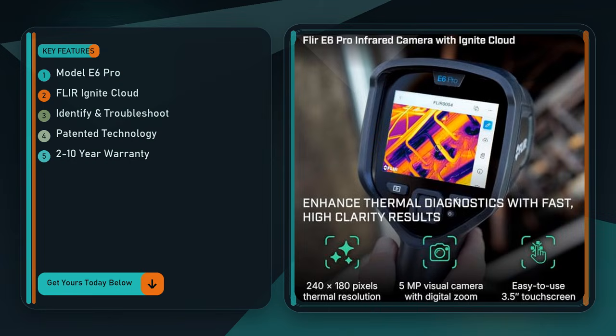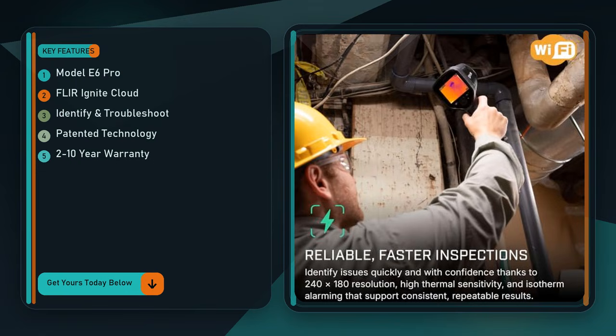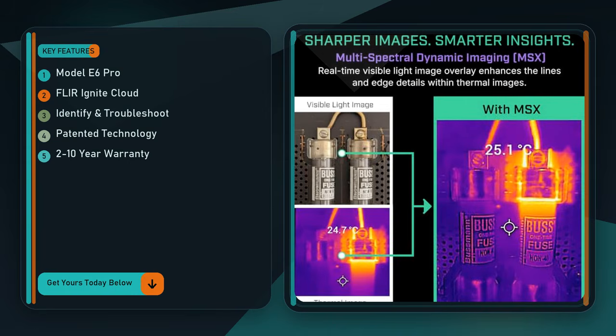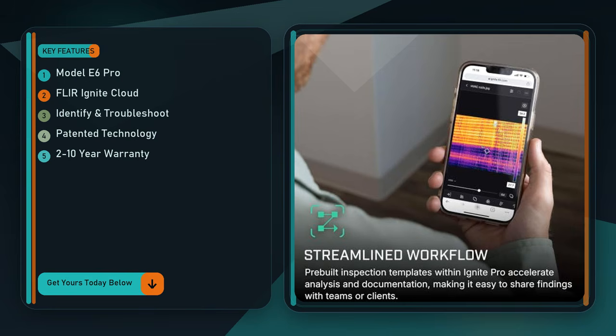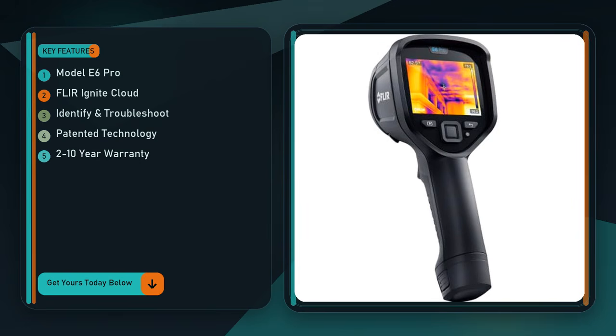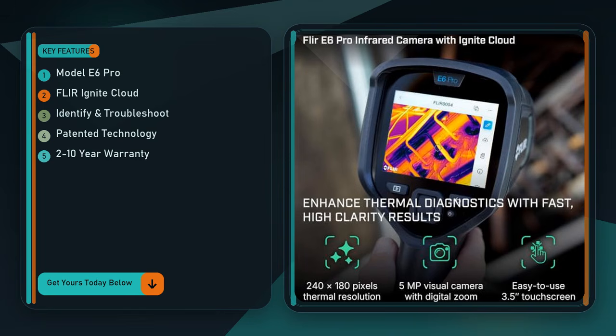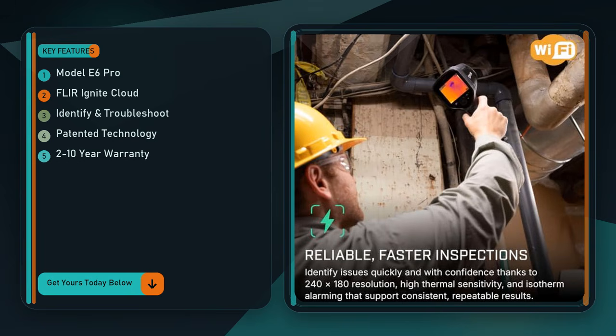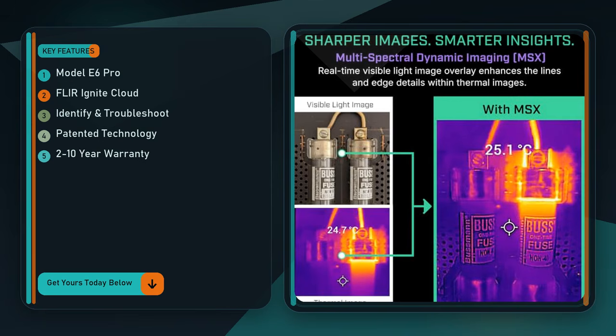Now let's talk about the menu system. The interface is fairly intuitive, but there's a learning curve if you haven't dealt with thermal imaging before. You can toggle between several palettes, ironbow, rainbow, black hot, etc., to highlight different temperature ranges, and you can set custom alarm thresholds that trigger an on-screen warning when a hot spot exceeds a preset limit. In practice, that alarm function saved me a few minutes during a preventive maintenance sweep. I set the alarm at a threshold for a series of motor bearings, and the camera beeped the moment one bearing started heating up, letting me zero in without scanning each component manually.